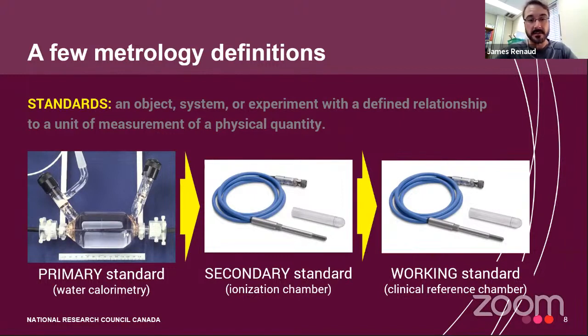Finally, the third level standard, the standard which is periodically calibrated against the secondary standard, is known as the working standard. We don't usually use the term working standard, as far as I can tell, in medical dosimetry. You might refer to it as a clinical reference chamber, or a local standard. But this is essentially the clinic's standard that serves to, say, calibrate all the linacs and is sent to the NRC periodically for recalibration. Working standards are expected to deteriorate and are no longer considered traceable to a national standard after a certain period of time. And working standards are used in the field to calibrate instruments.